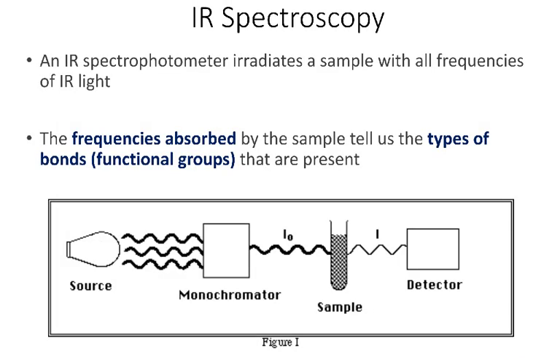Here is a fairly simple schematic of how an infrared spectrometer works. We have a light source emitting infrared radiation and a monochromator that selects a specific wavelength. We shine that wavelength through the sample, knowing the intensity before it enters the sample, then measure the intensity after it exits. If the intensity decreased, we know the sample absorbed that radiation. We then scan through a whole range of wavelengths and frequencies to see at which frequencies the sample absorbs infrared radiation, and use that information to identify functional groups in our compound.